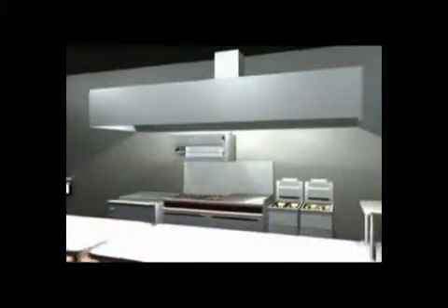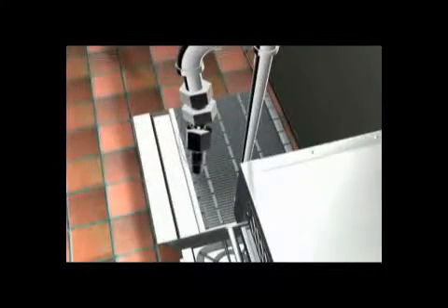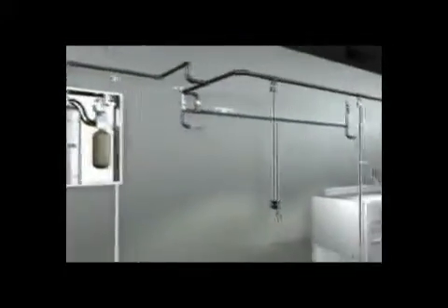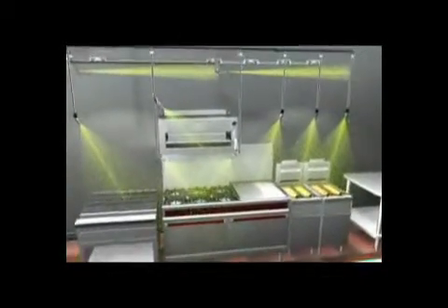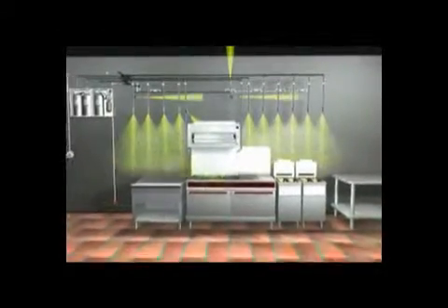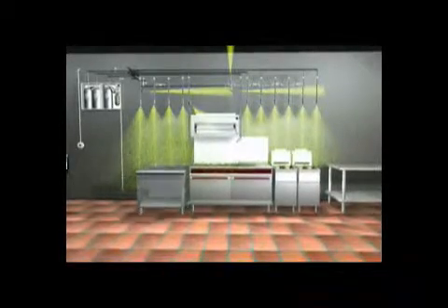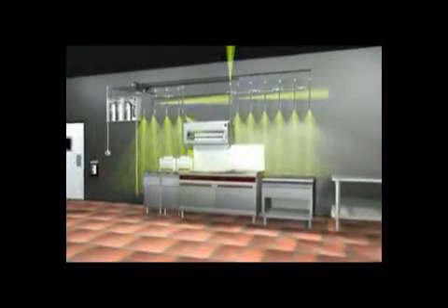With the R-102, you have two design options. The primary is an appliance-specific design, which allows you to aim the nozzles at specific areas on the appliance. This is considered the most economical design because the chemical is directed exactly where it's needed to most efficiently suppress the fire. The alternative installation is overlapping appliance protection, where nozzles are installed in a straight line and provide overlapping discharge patterns. Using this layout, you can move or replace appliances, and as long as they stay within the fire-free zone, they will be protected.